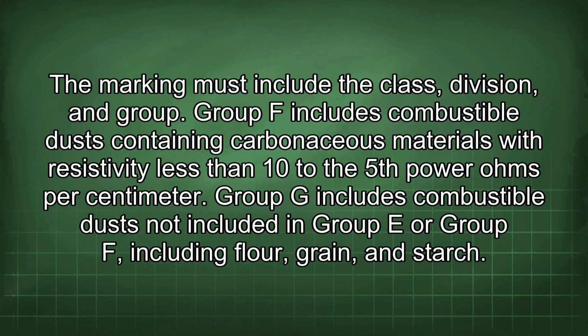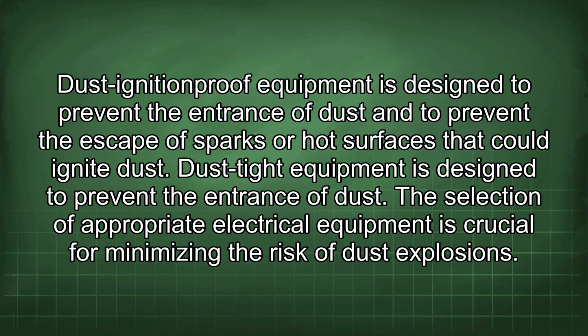Group F includes combustible dust containing carbonaceous materials with resistivity less than 10 to the 5th power ohms per centimeter. Group G includes combustible dust not included in Group E or Group F, including flour, grain, and starch. Dust ignition-proof equipment is designed to prevent the entrance of dust and to prevent the escape of sparks or hot surfaces that could ignite dust. Dust-tight equipment is designed to prevent the entrance of dust.